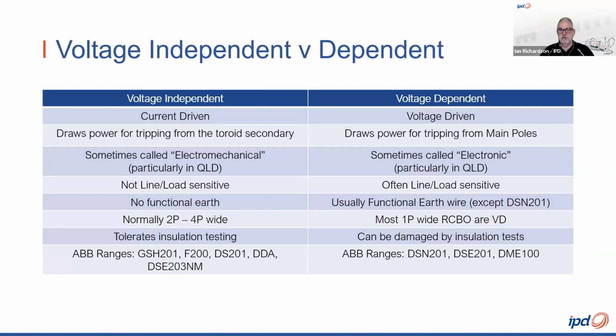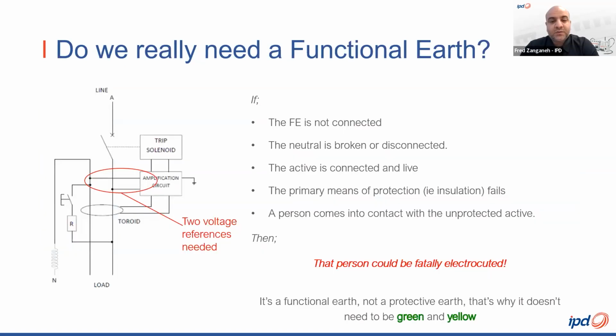That's very true. This table highlights the differences between the voltage independent and the voltage dependent types of relay. We can see that often the voltage dependent RCD has an additional connection called a functional earth. Yeah, the functional earth connection provides an additional safety level for voltage-dependent RCDs. It provides a second voltage reference in case of neutral wire failure.